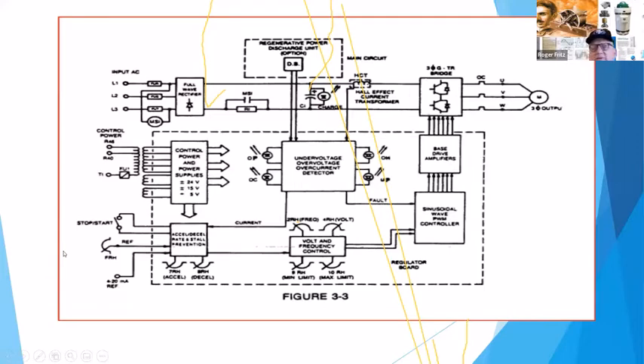So back to the original VFDs. This is actually a circuit drawing that I had from the early 80s, before we had all the digital capability. And you can see that everything was done in what they called analog. So these were small little potentiometers inside the VFDs that you tweaked with a tiny little screwdriver. And so as you set up the PWM and the setups, you had to adjust the voltage, the tuning frequencies, the upper limits, the lower limits, all in an analog format. The frequency and the carrier frequency, all that decel, accel, were all adjusted by potentiometers.